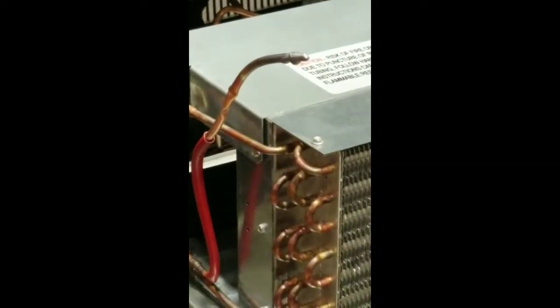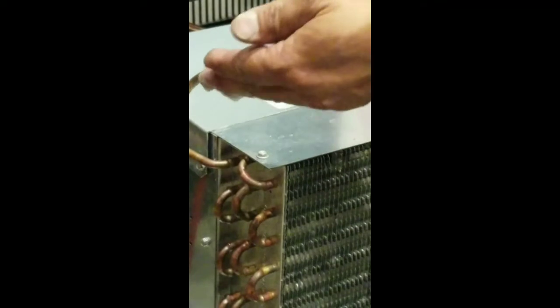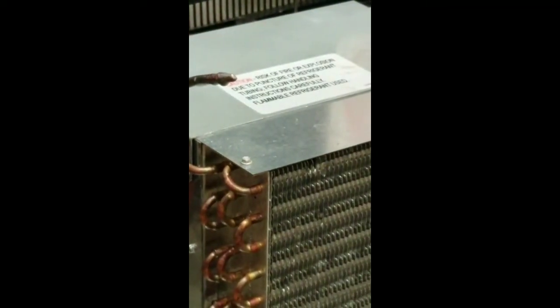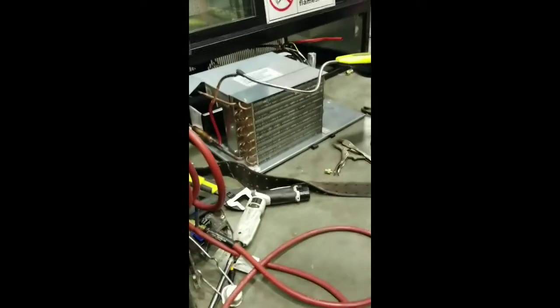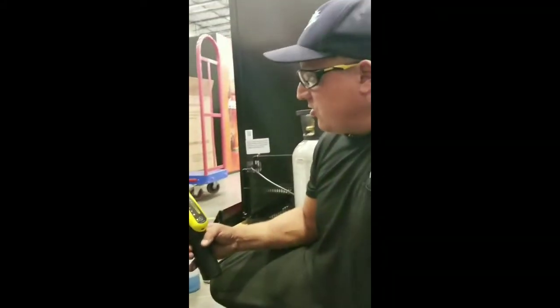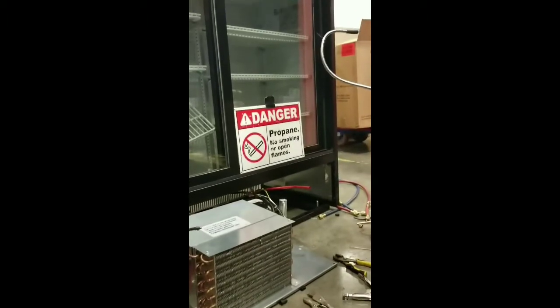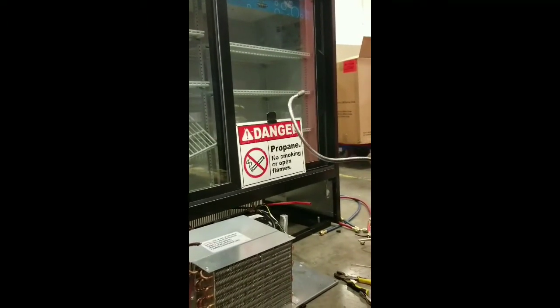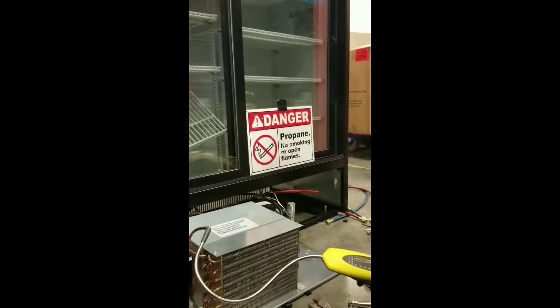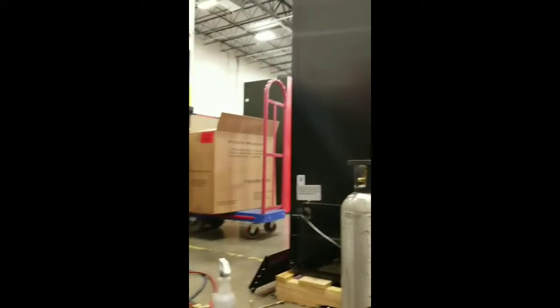So we're going to take these off now. We're going to put some soap on them. Make sure we don't see anything crazy coming out. Grab our little leak detector. This one was sort of in question. I'm not sure if that picked up from myself. Or what it could have picked up on. Still might be a leak. We gotta solder it one more time.